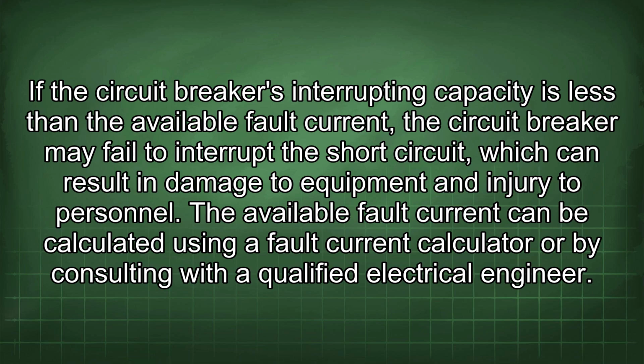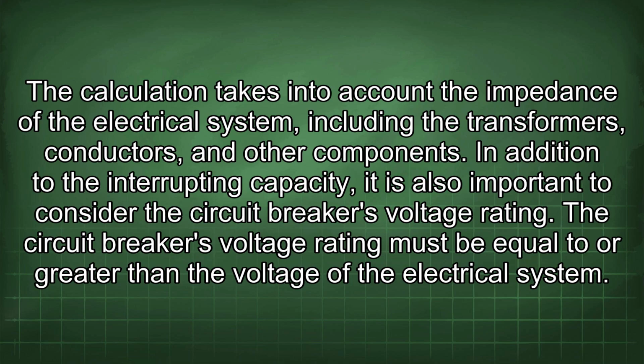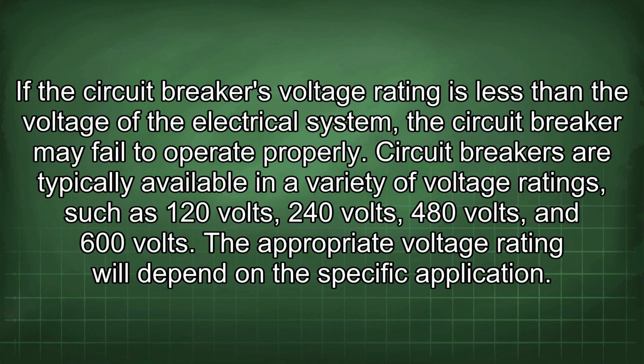The available fault current can be calculated using a fault current calculator or by consulting with a qualified electrical engineer. The calculation takes into account the impedance of the electrical system, including the transformers, conductors, and other components. In addition to the interrupting capacity, it is also important to consider the circuit breaker's voltage rating. The circuit breaker's voltage rating must be equal to or greater than the voltage of the electrical system. If the circuit breaker's voltage rating is less than the voltage of the electrical system, the circuit breaker may fail to operate properly.